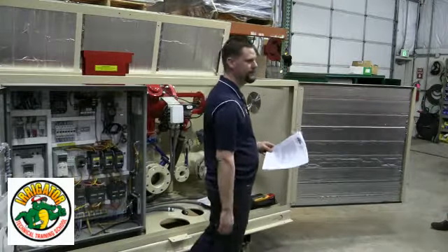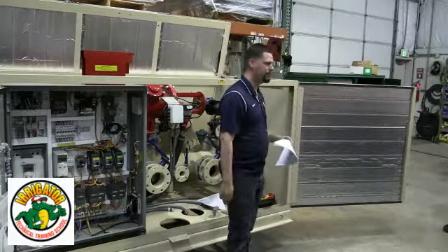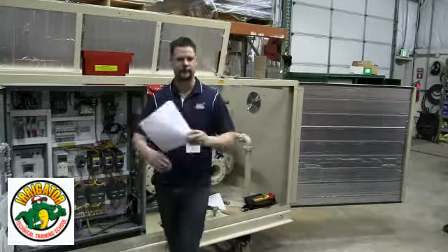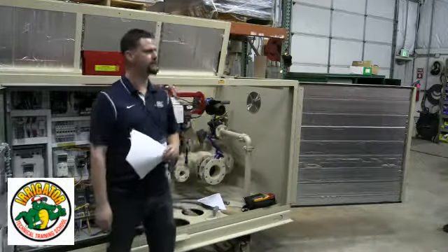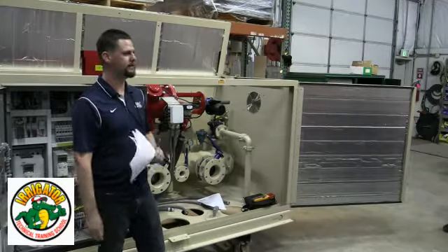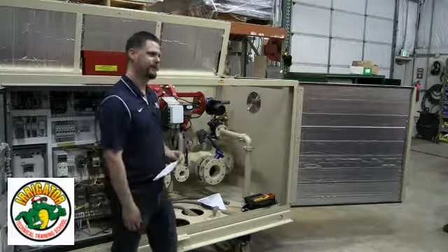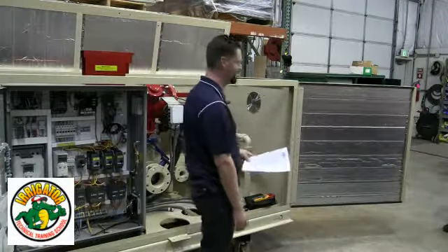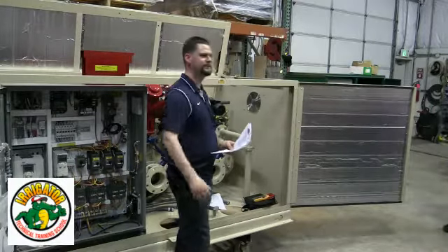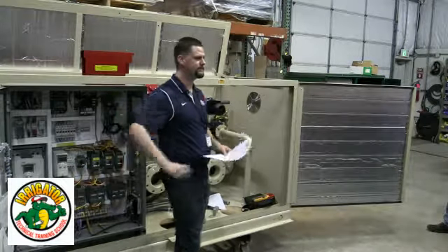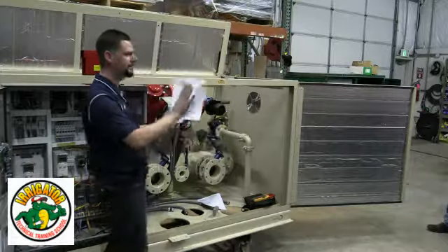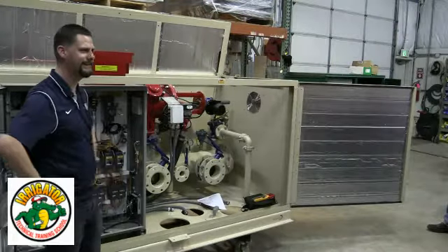Here's another funny story for you. I get calls every year. My pumps won't stop. My pumps are always running. Well, go turn them off. What happens? Well, the pressure drops. Well, you've got water going somewhere. No, I don't. Okay, shut the isolation valve to the pump station. Bring it up to pressure. Okay, now turn them off. Well, son of a gun.